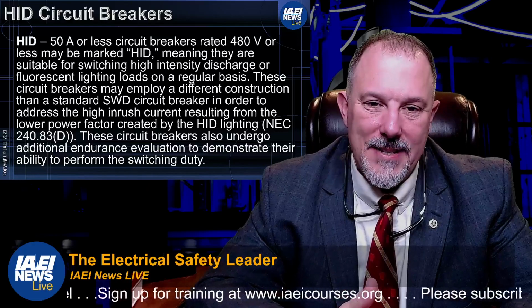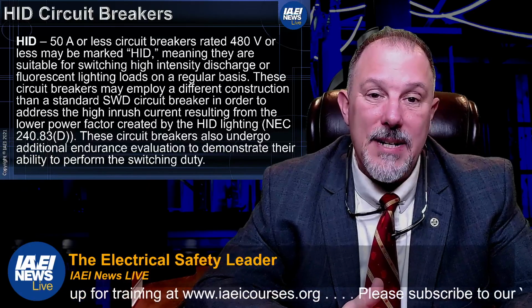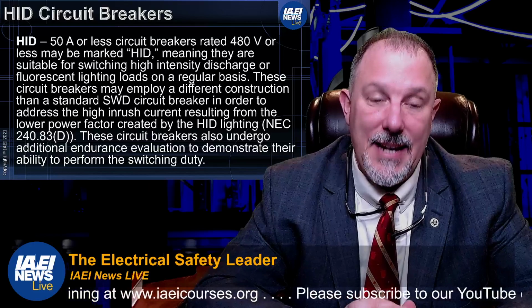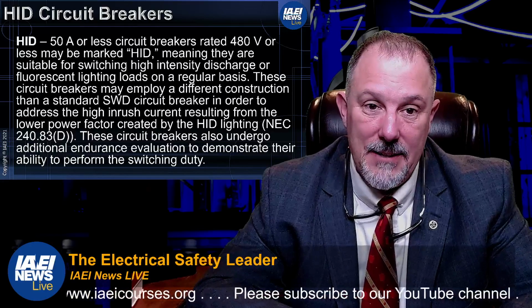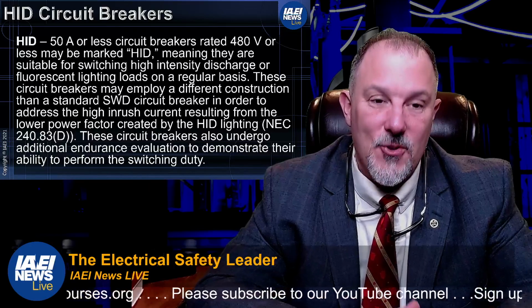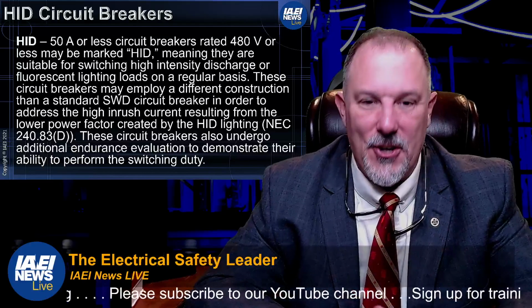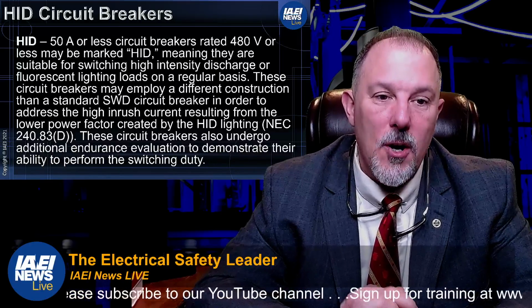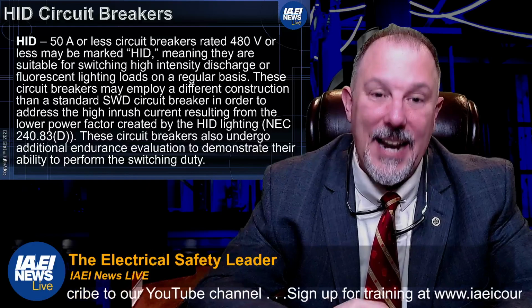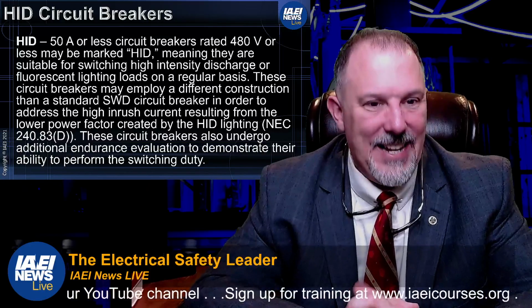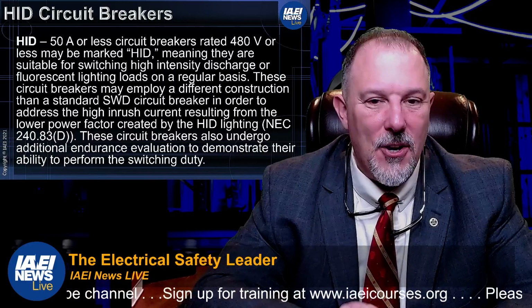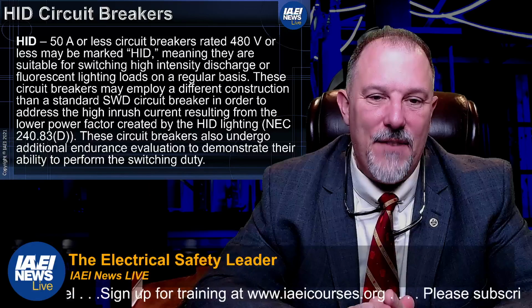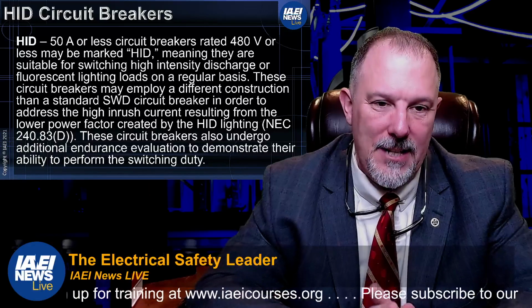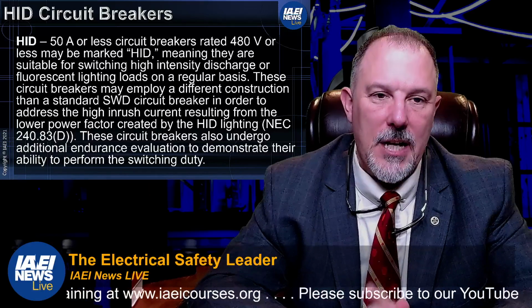On a regular basis, these circuit breakers may employ a different construction than the standard SWD circuit breaker in order to address high inrush current resulting from the lower power factor created by HID lighting. These circuit breakers also undergo additional endurance evaluation to demonstrate their ability to perform the switching duty.